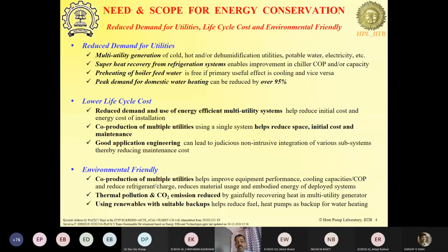Now, co-producing multiple utilities not only helps with respect to reducing space, cost, and other things, it also helps improve the equipment performance. So low energy consumption. Low energy consumption means low fuel input or electrical input. That means low emissions. Then since the cooling capacity also goes up, the size of the system, compressor size and heat exchangers and others can also be optimized and reduced, and that can help you reduce the refrigerant charge. So reduce refrigerant charge, and if the refrigerant is not very environment friendly, then again reducing the refrigerant charge helps in meeting the environmental concerns also.